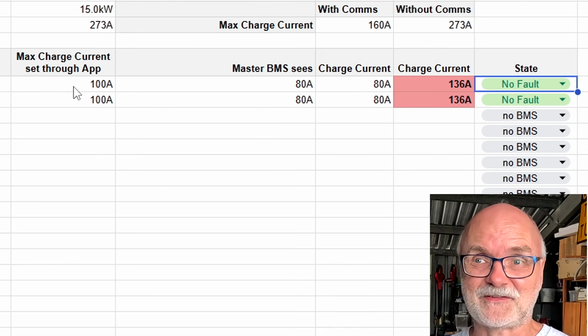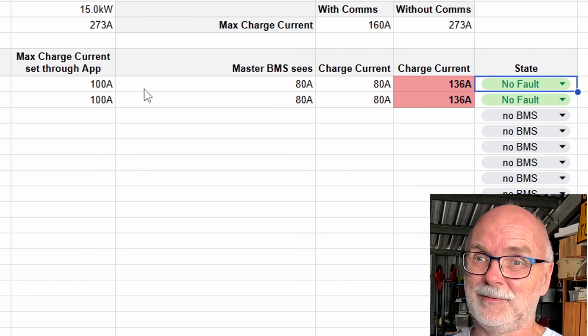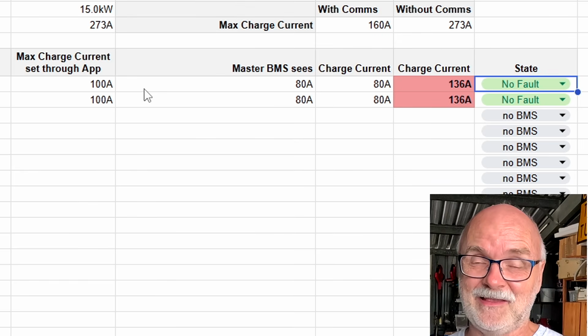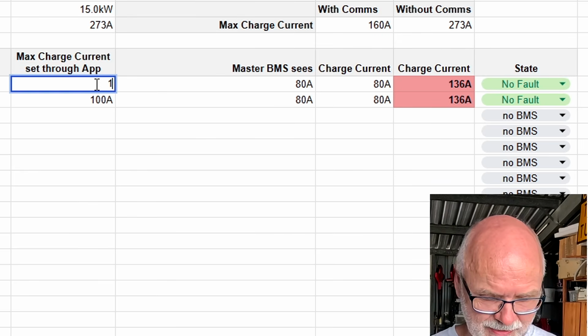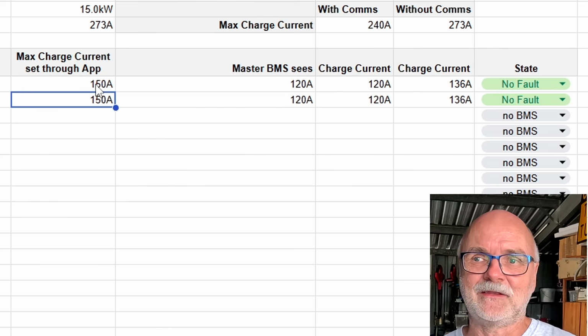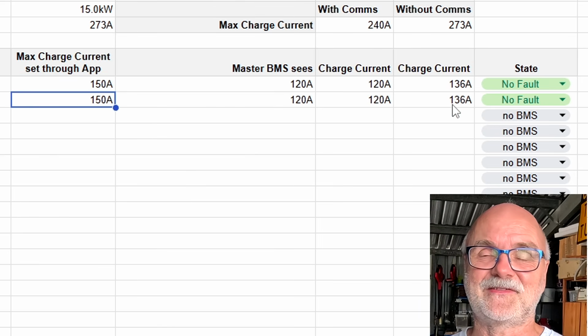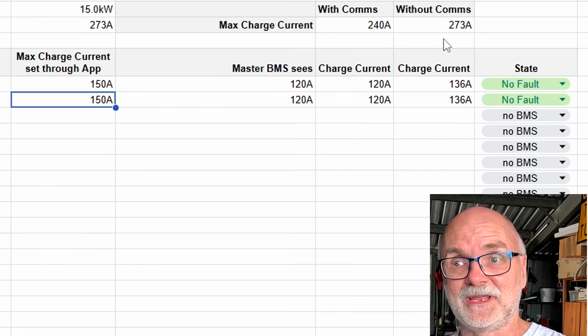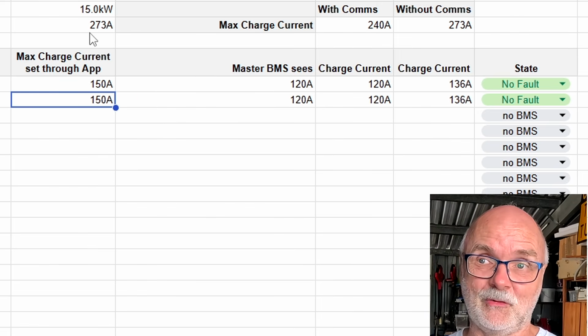Yeah, don't just increase this value here because you're getting close. Ensure your cabling and everything else is as per the standard as well. And then you can increase your BMS to 150 amps and you are in the safe place again, even without communication and this size of solar system.